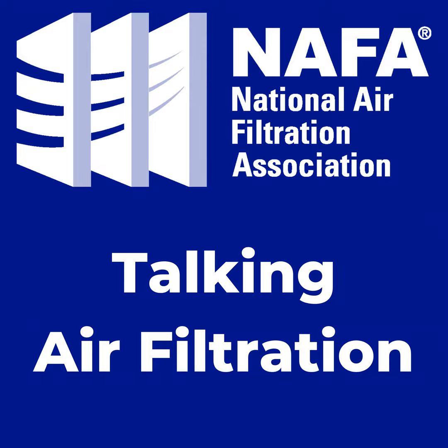So at Purdue, currently, research is funded by ASHRAE. Hopefully the data should be out soon, but they're making urban aerosol, using a thermal flame generator with a salt rod that's creating a really nice particle size distribution. So you're loading these fibers with more particles that would more represent what's actually in the air and what these filters are actually seeing. And these particles could do a good job of measuring that efficiency loss because you're coating with the fine fibers like the Appendix J, and you can see how that efficiency is being affected over time.